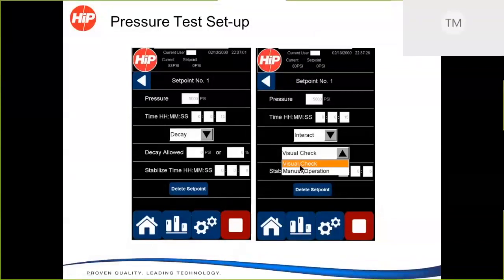A visual check might be, you know what, I want to pause a test, and I want to physically look at my piece that I'm testing and see if there's any fluid leaks that I can see. A manual operation might be, I'm testing a needle valve, and I want to actually open the valve and see something happen, and then close the valve again, and then when I'm done, start the test again. So think of it as a way to pause a test, do something, and then restart the test again.